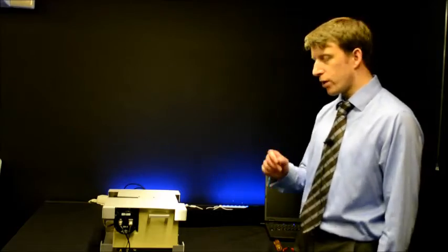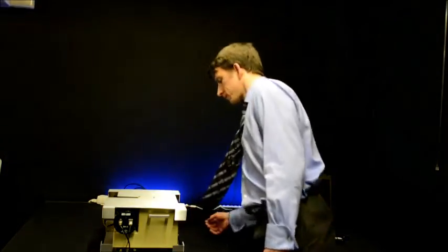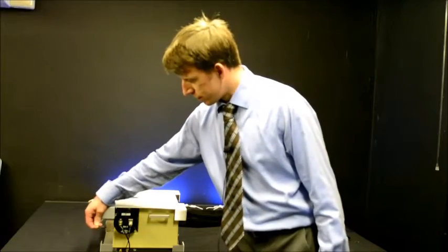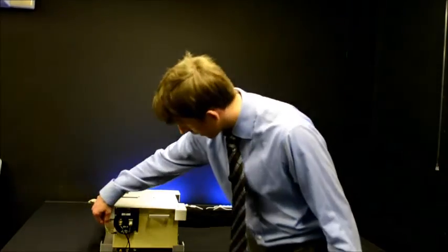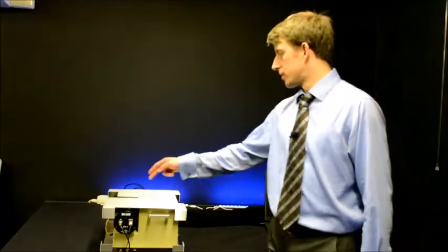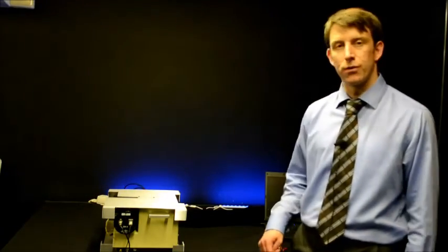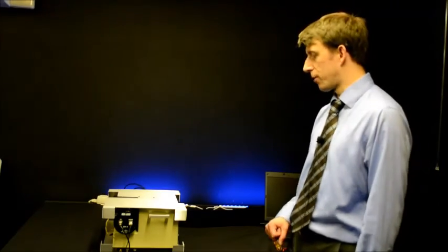This unit has 1 mains input and 1 USB input found to the rear, and beside the photomultiplier a 3-pin connector is provided, which leads to a thermocouple on the unit to monitor the temperature in the EnviroBox for the purposes of the EnviroBox controller.